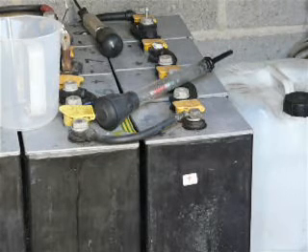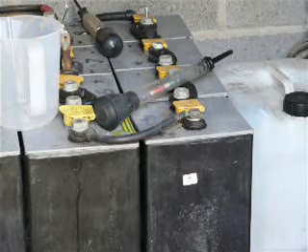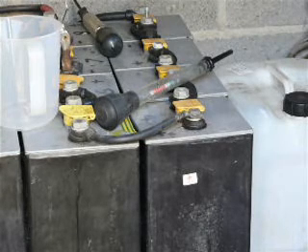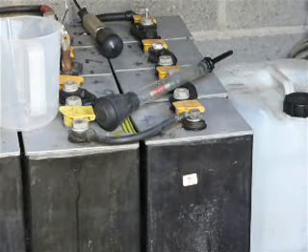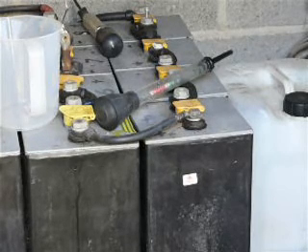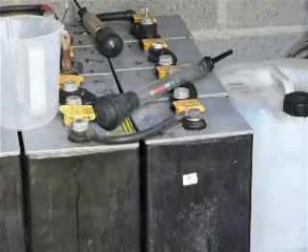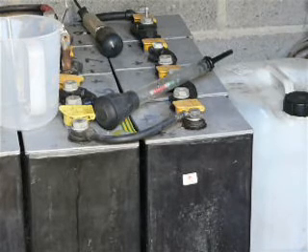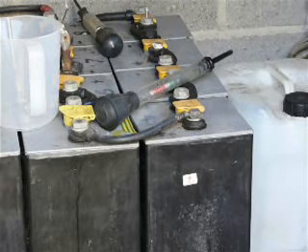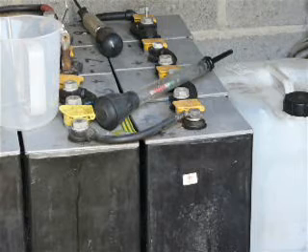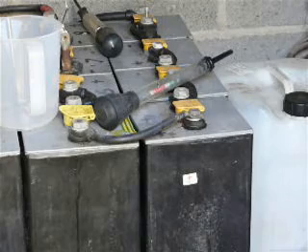For a battery pack to act as a reliable power source, then it must be kept fairly well charged most of the time and never discharged below 50% of its rated capacity. As a rule of thumb, I never discharge below a specific gravity reading of 1.200. And of course, in this video, you can see a hydrometer on the battery pack. A hydrometer is used for measuring the specific gravity of the acid. There's shed loads more on this subject in the book.